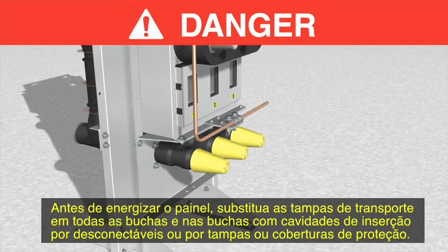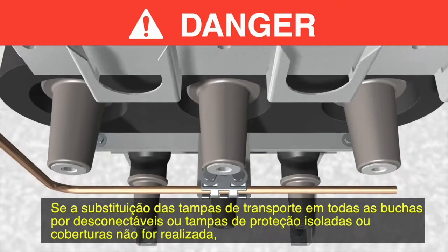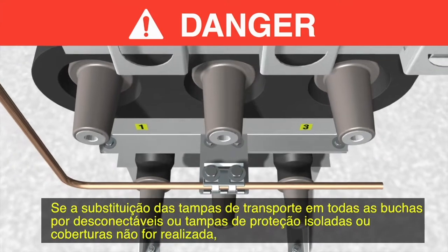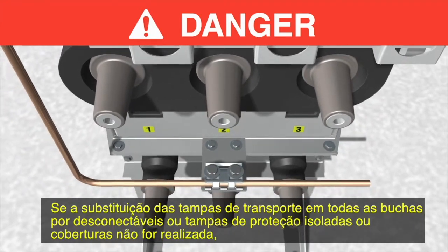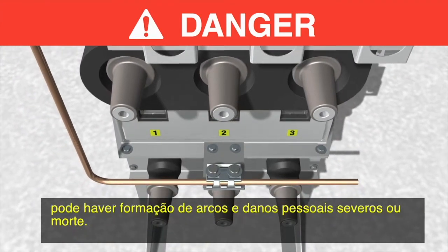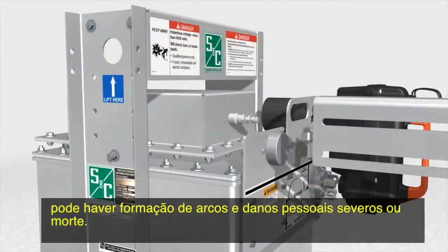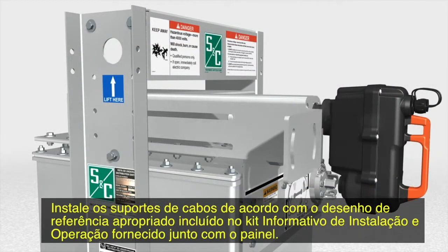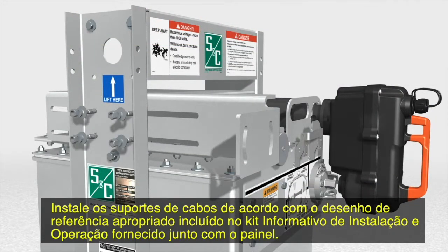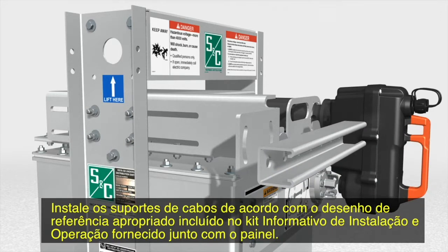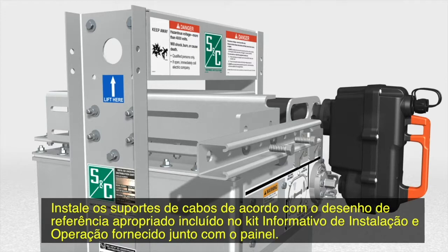Before energizing the switchgear, replace the shipping covers on all bushings and bushing wells with elbows or insulated protective covers or caps. Failure to replace the shipping covers on all bushings with elbows or insulated protective covers or caps can result in a flashover and serious personal injury or death. Install the cable support brackets in accordance with the appropriate reference drawing included in the installation and operation information kit that came with your switchgear.